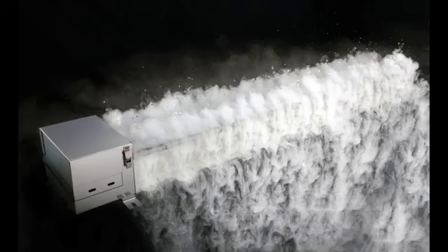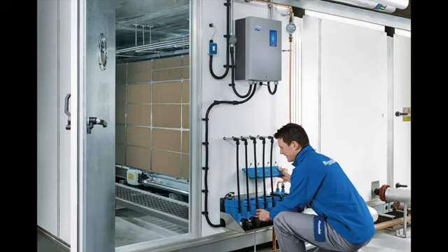Another type are ultrasonic humidifiers, and these tend to have smaller outputs, so are useful for small areas like a humidor or a display cabinet. And lastly, evaporative humidification, where moisture is evaporated directly from a wetted surface. And these are a great option for AHUs if space allows. Any cold water humidifier will typically take up a bit more space inside the duct than a steam humidifier's steam pipe. So for AHUs, the duct section length can be a deciding factor in the product selection.